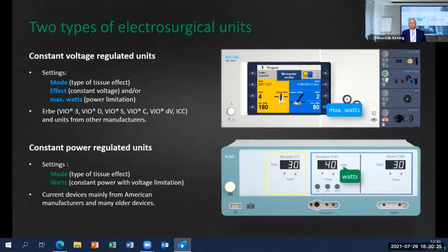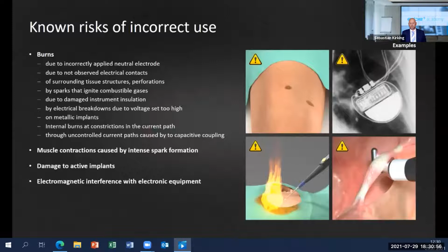The other lectures today will discuss insulation failures, capacitive coupling, fires, and possible risks of misuse in detail. Therefore, these pictures shall only be an introduction to these important topics. So please be aware that incorrect use of electrosurgery can lead to high current density at other parts of the patient body, can damage active implants, and that the spark formation can ignite flammable gases and cause fires in the operating room. All these risks are well known and published. A good and reliable source of reference and guidance is this technical report by the International Electrotechnical Commission. As you see, even though electrosurgery is one of the most used surgical technologies and known for almost a century now, it must be well understood and educated.